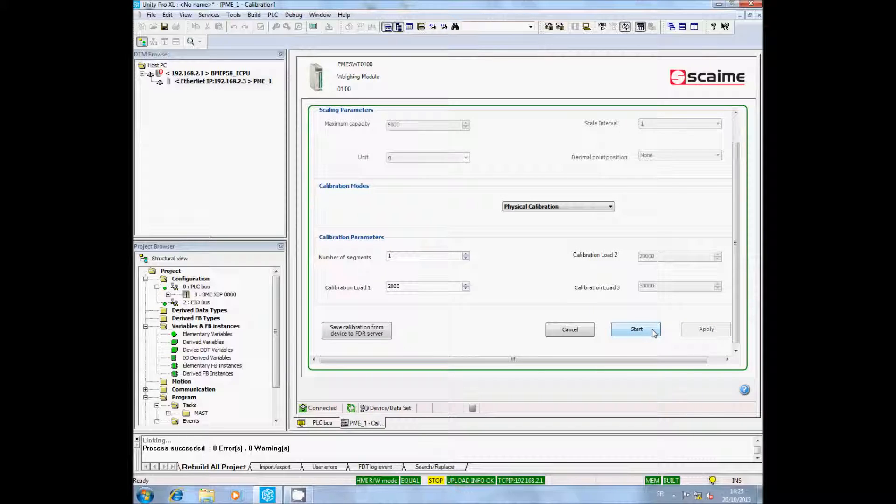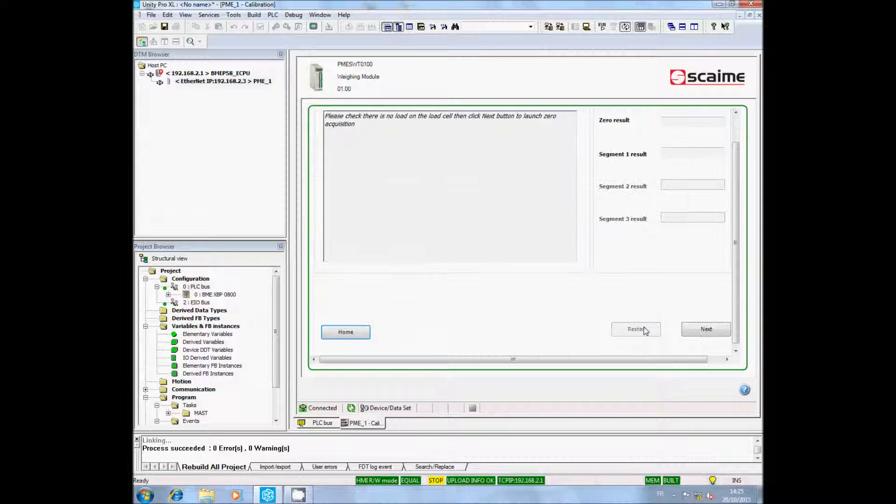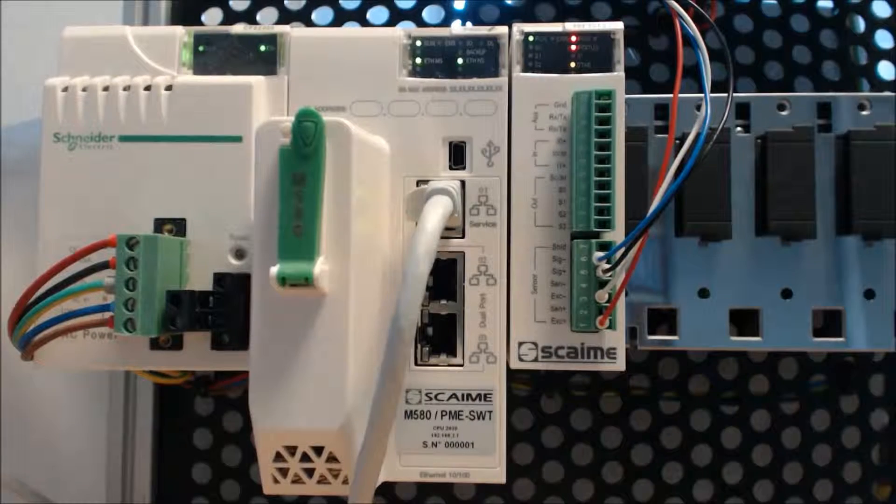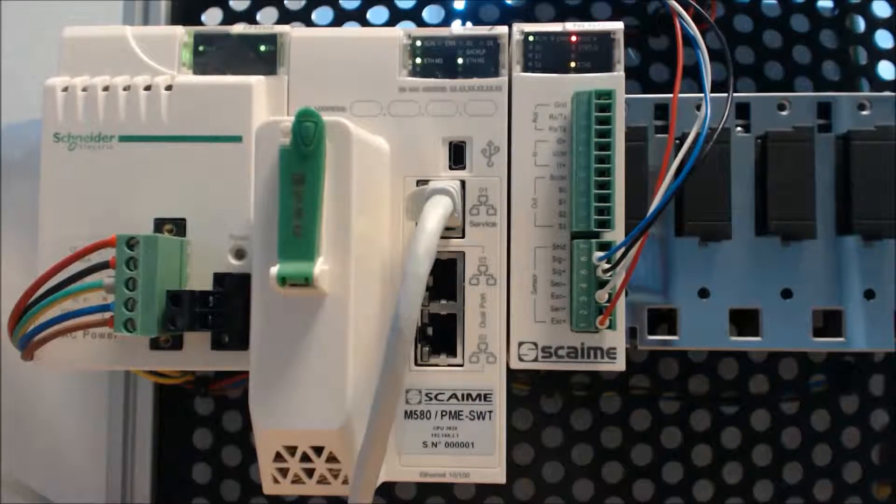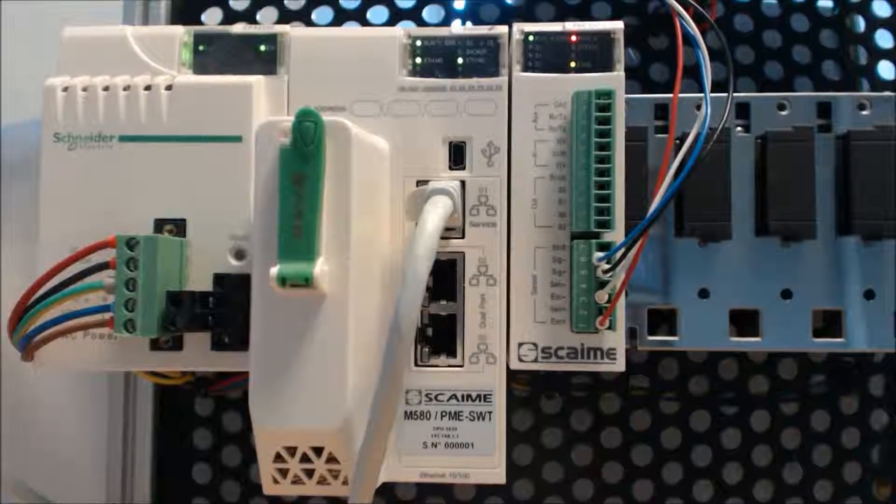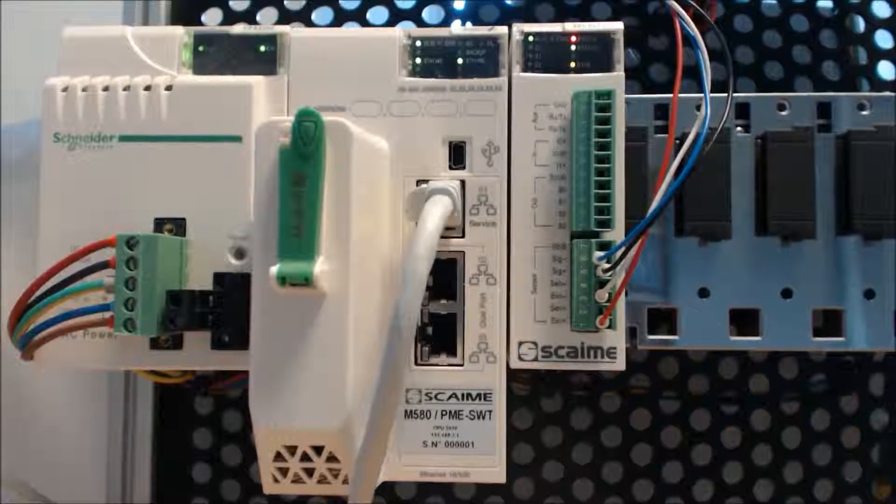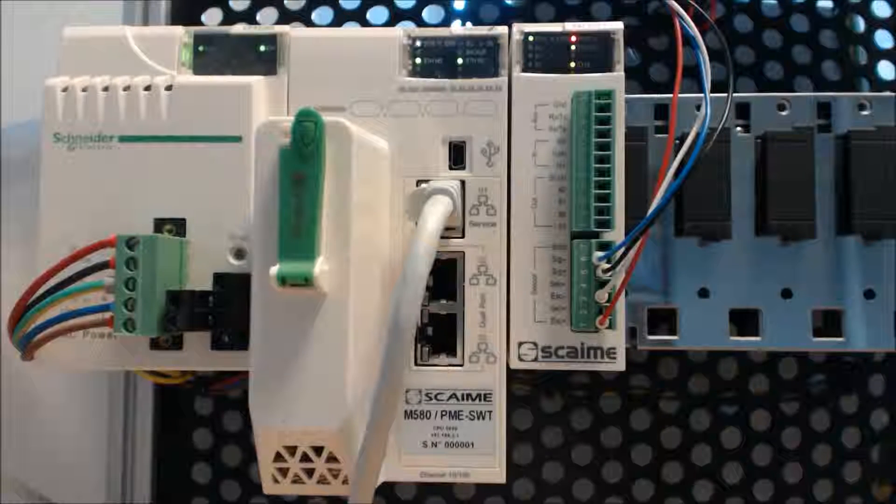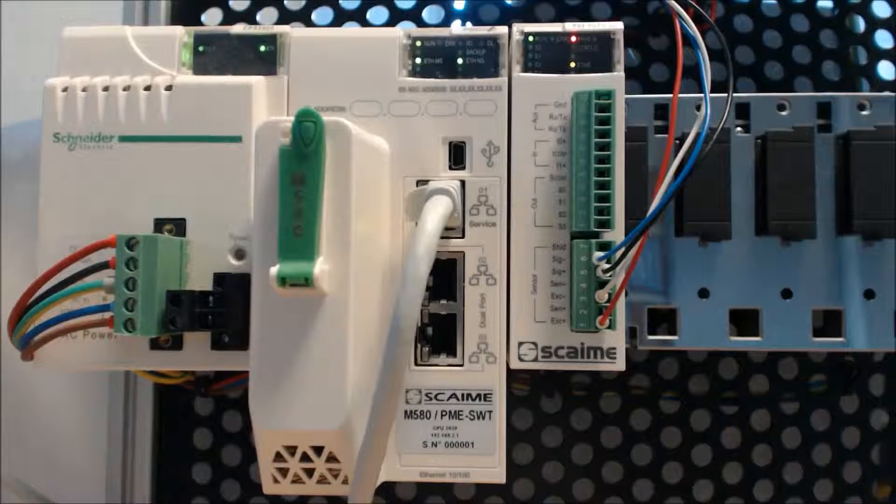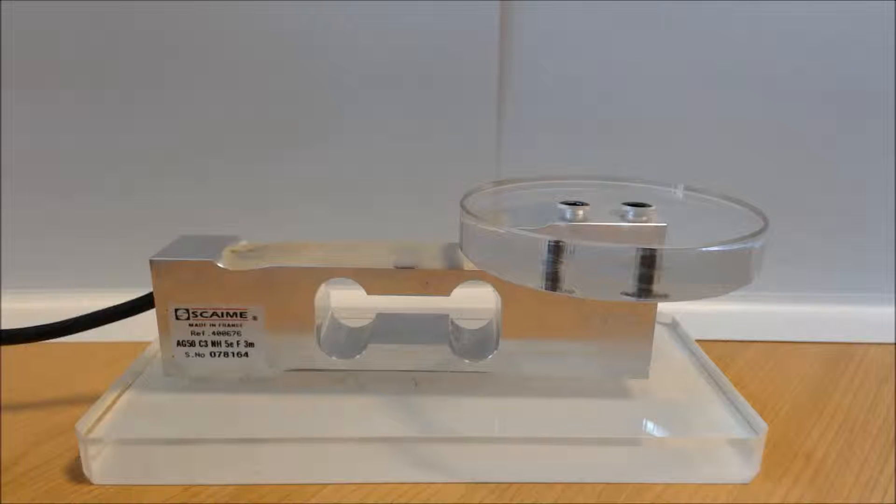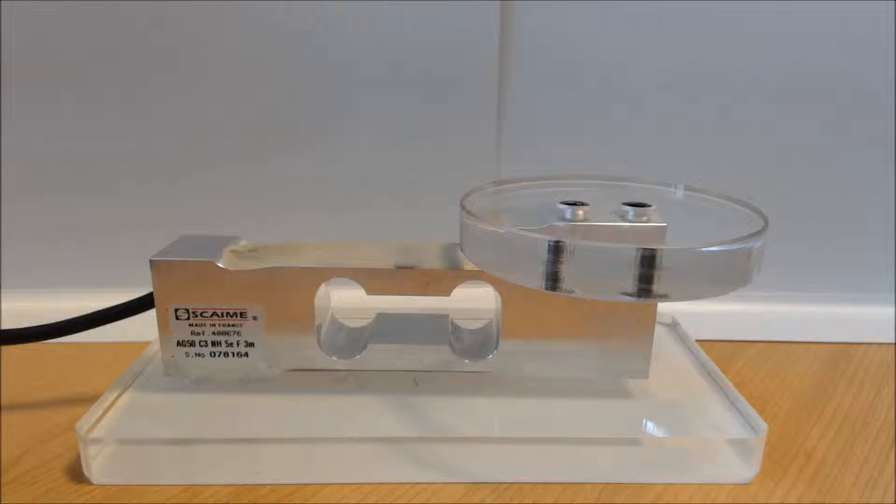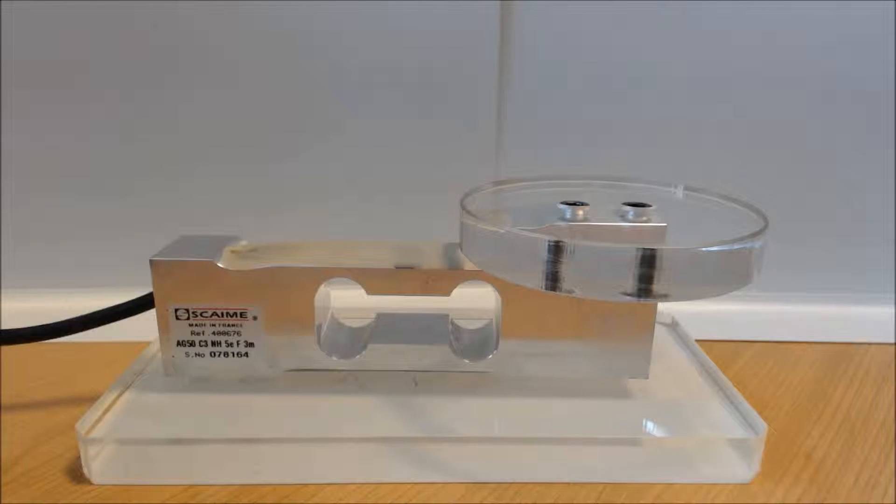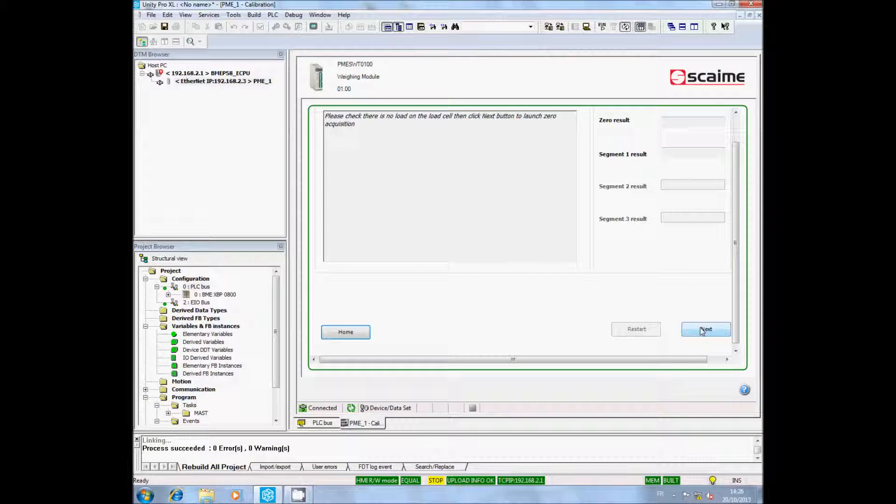The calibration software starts. You can see the status LED, which was blinking in red, will begin to blink in green. That means the calibration is in progress. The software asks you to check that there is no weight on the scale. Once this verification is done, you can click on Next. The zero will be acquired.